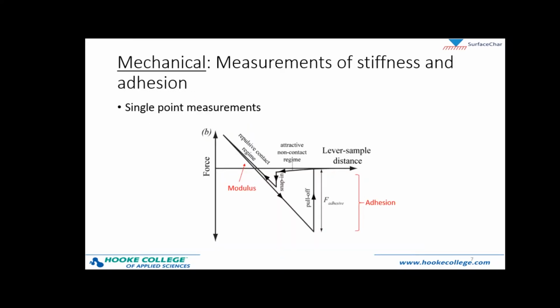Now what I just showed was an imaging measurement that AFM can do based on mechanical properties, but it can also do single point measurements to get more quantitative measurements now of important properties such as stiffness or modulus and adhesion. Those single point measurements are shown in the schematic before, where you literally at a single point just poke the surface with your cantilever, and you measure what's called these force versus distance curves at these individual points on your sample, where the force is typically in units of nanonewtons and the distance is typically in units of nanometers, so tens, hundreds of nanometers, maybe even up to a micron.